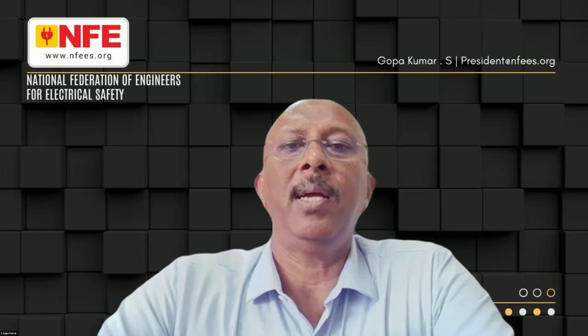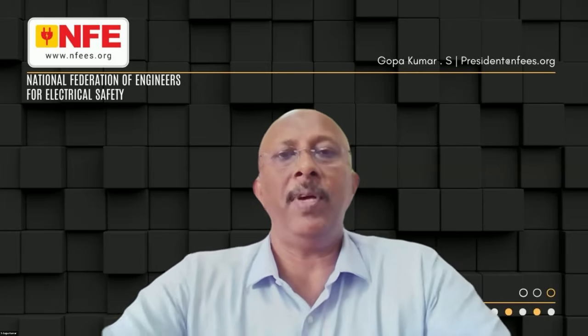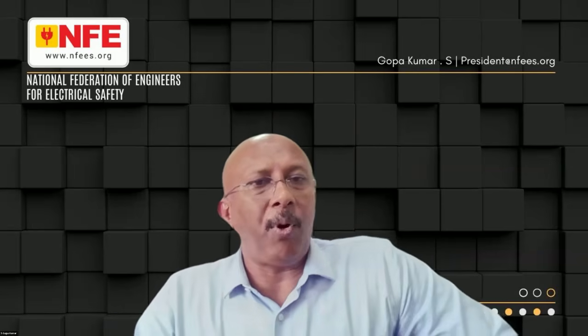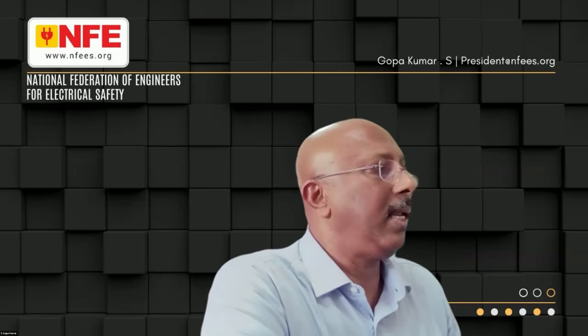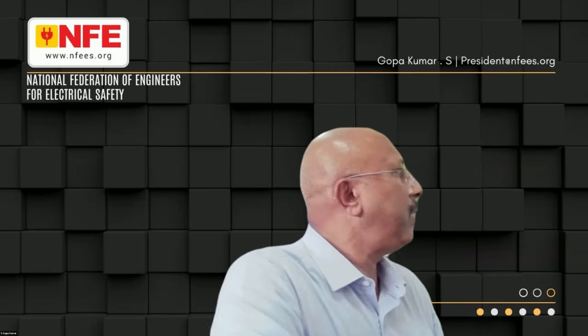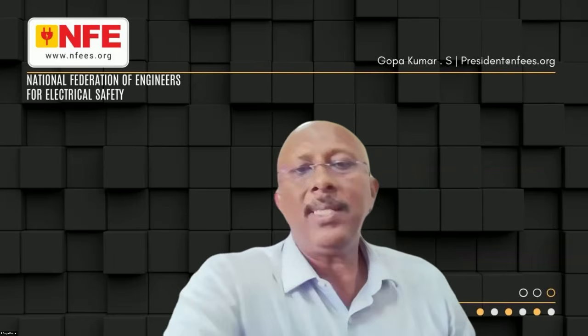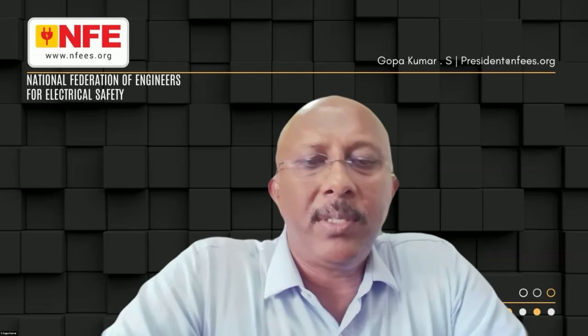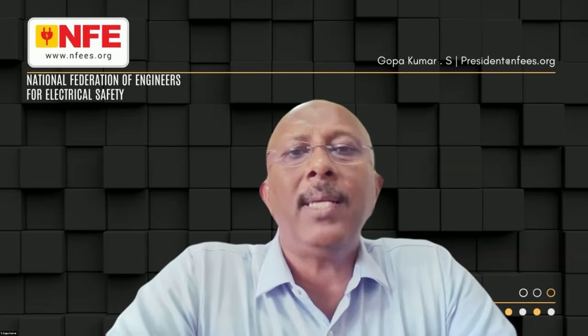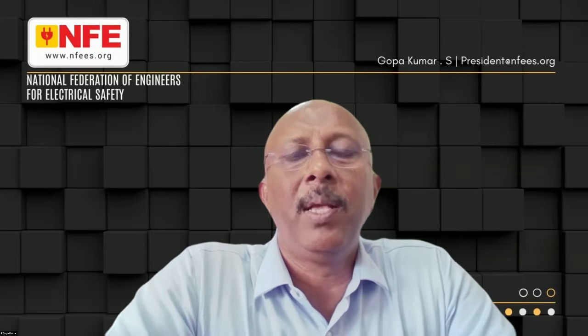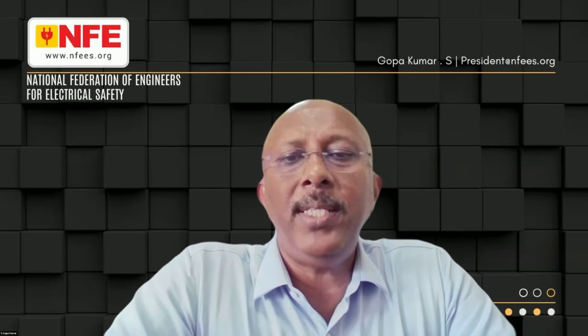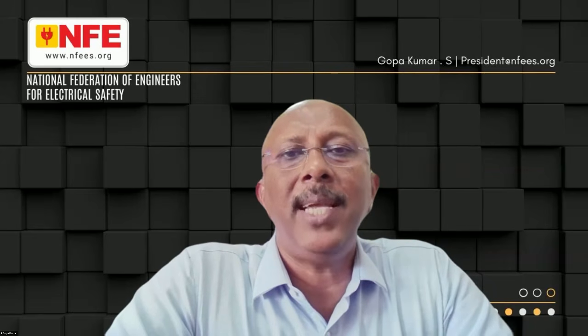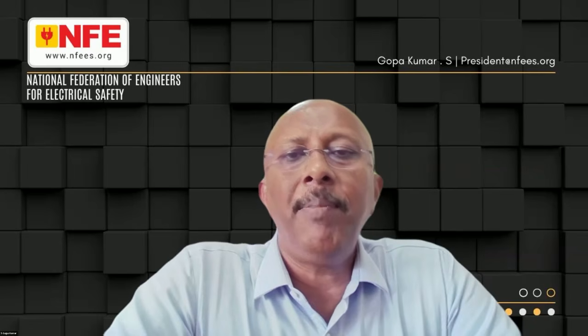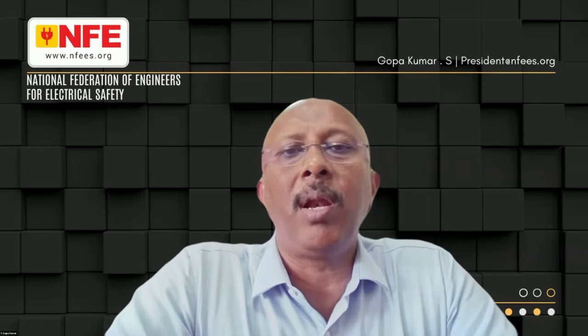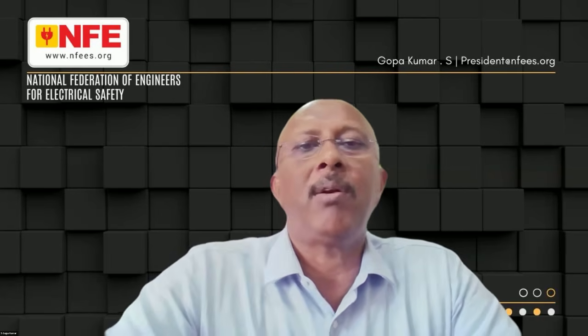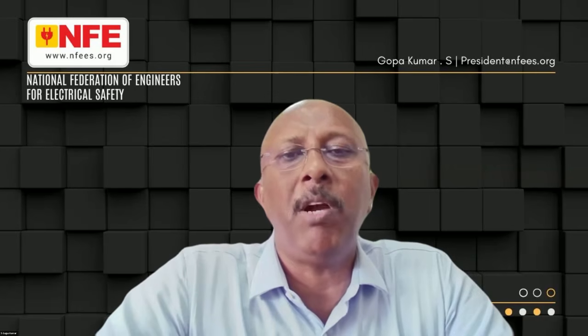What safety measures should be taken for the UPS room in a hospital? Of course, the UPS room is a very important subject. Let me try to share the screen and explain one subject. I think I missed that particular subject. UPS, the challenge is, modern UPS uses the incoming neutral as the reference for its PCB. During the changeover from mains to DG or from DG back to mains, sometimes the neutral misses, meaning the connection to the neutral is missing. That means the reference to the electronics in the UPS is missing. As a result, UPS malfunctions.